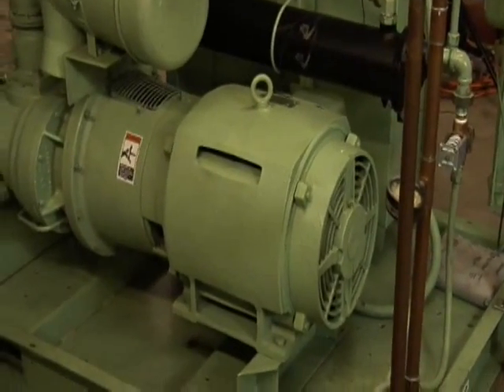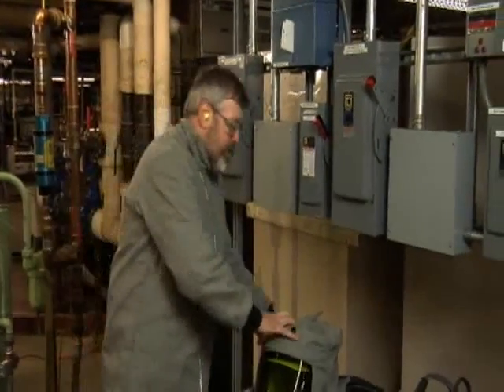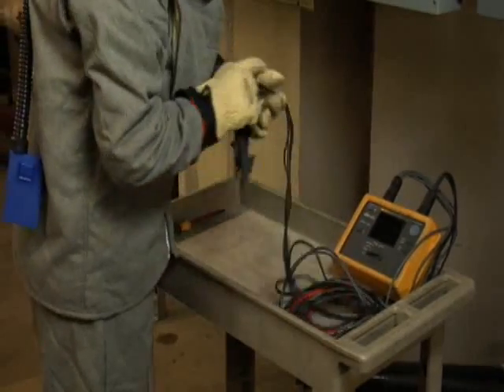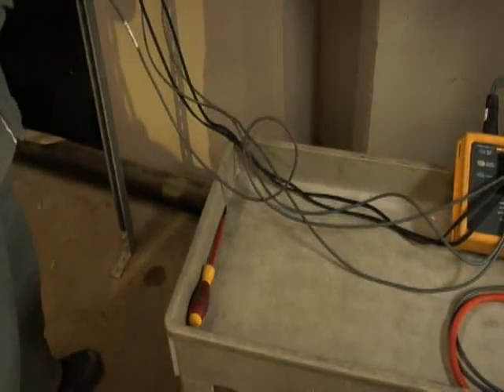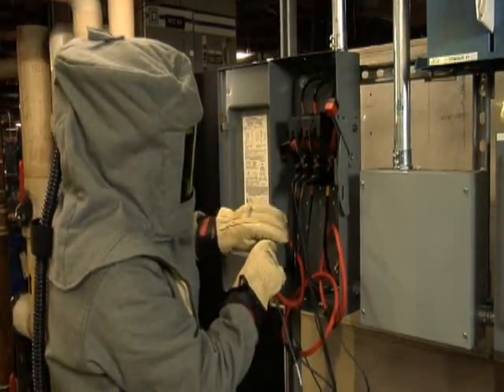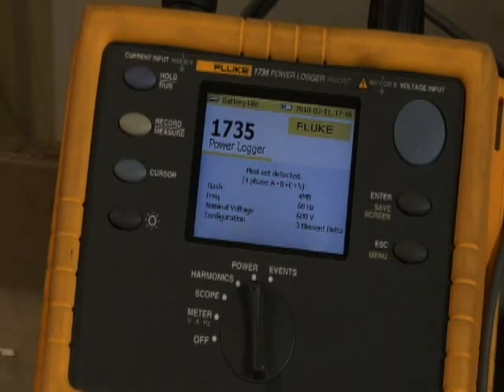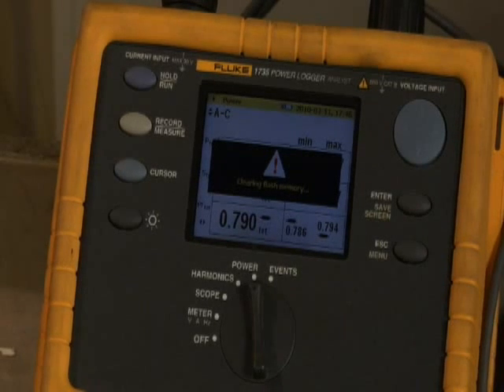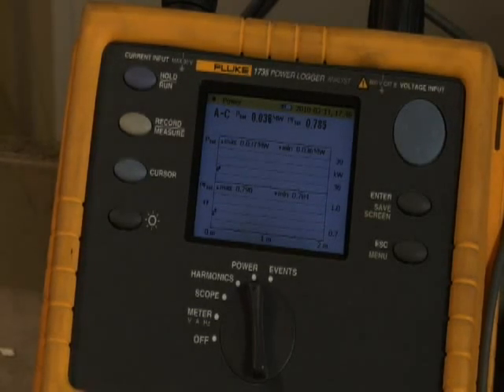Keep moving your logger downstream to large loads and find out how much energy they are consuming. This compressor is a good example of a load that's big enough to cause problems with your electrical bill. Again, make sure you are wearing the proper PPE for the job. Always stand to the side as you open and close your doors. Connect your color-coded voltage leads to the correlating connections. Connect the flex current clamps to the matching connections, making sure that all connections are correctly made. Flexible current clamps can be ideal for hard-to-reach locations. Once you've completed your connections, go to the power screen and make sure your leads are detected and your configuration is correct and power is being measured. When ready, push the measure record button. Hit enter to accept the warnings that previously recorded data will be lost. The logger clears its memory and begins recording data. Notice when your peak demand occurs and compare it to your operational schedule. These charges can be managed effectively by analyzing the data from your power logger.